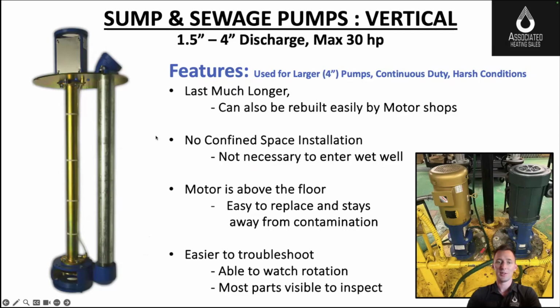Some disadvantages: these vertical pumps require some maintenance. There's a lubrication line, so weekly lubrication would probably be recommended there. And you can't put them into deeper pits. As you put them into a deep fiberglass basin or pit, these vertical pumps get longer and they'll burn up more quickly as that long single piece shaft wears into those bearings more rapidly.